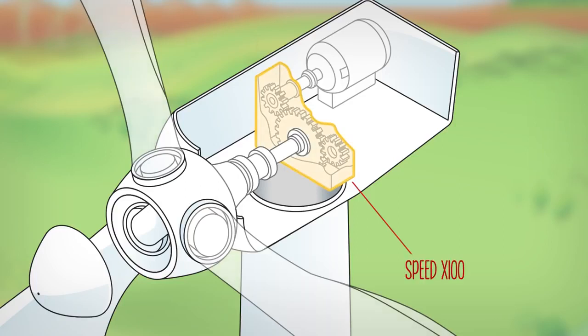That is the mission of the gearbox, which raises the speed over 100 times and transfers it to the high speed shaft. The high speed shaft, that rotates at up to 1500 revolutions per minute, is connected to a generator.